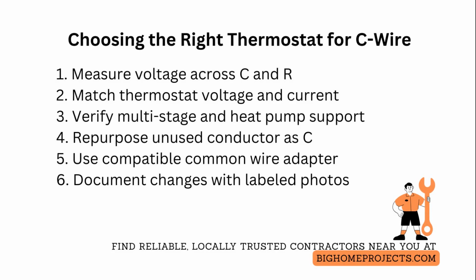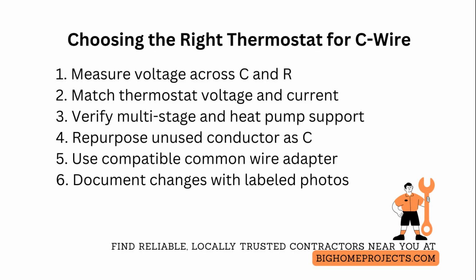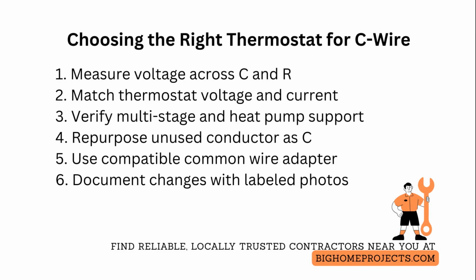For systems that use heat pump reversing valves or two-stage equipment, verify the thermostat supports the exact number of heat and cool stages and O and B wiring conventions. Program legacy heat pump settings manually if the installer menu defaults to conventional settings.